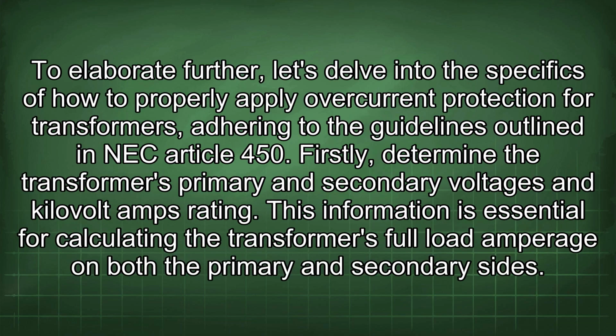To elaborate further, let's delve into the specifics of how to properly apply overcurrent protection for transformers, adhering to the guidelines outlined in NEC Article 450. Firstly, determine the transformer's primary and secondary voltages and kilovolt amps rating.